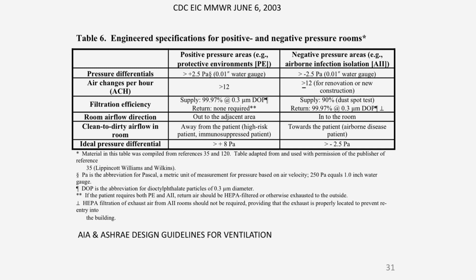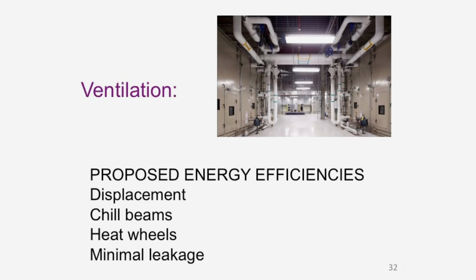The ideal pressures are down below. We only put the minimum into the standard, but the ideal is what we would really want to go for. And 8 pascals is a reasonable amount, but some institutions that I've worked with think they need more, and therein is a rub for energy management and overdoing it for a variety of reasons. So ventilation is really our target. We have proposed energy efficiencies that include displacement ventilation, chilled beams, heat wheels, and minimal leakage for the topics that we will cover today.